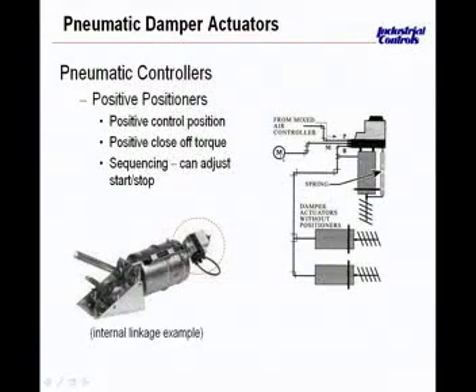And again, this is a box that may or may not look exactly like this, but it has the ability to have main air pressure. Let's say for the sake of conversation today, this is, let's pretend, 20 pounds of main air. And then from the controller, we have the branch line air pressure going into the P port, which is the pilot port of this positive positioner. Then with this feedback spring, if the controller or thermostat is saying, again, I should be at 50% open, if this stem is not extended out 50%, the positive positioner will say, hey, I'm not at 50%. I'm going to use 20 pounds of air pressure coming through this positive positioner.